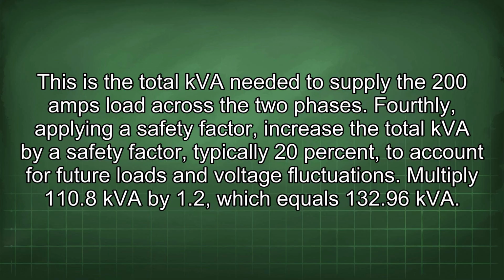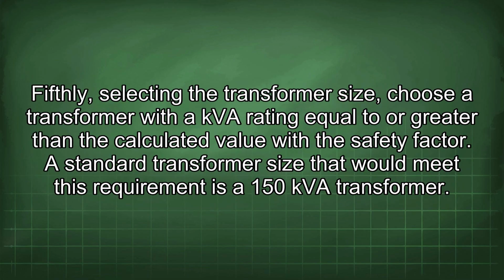Fourthly, applying a safety factor: increase the total kVA by a safety factor, typically 20%, to account for future loads and voltage fluctuations. Multiply 110.8 kVA by 1.2, which equals 132.96 kVA. Fifthly, selecting the transformer size: choose a transformer with a kVA rating equal to or greater than the calculated value with the safety factor. A standard transformer size that would meet this requirement is a 150 kVA transformer.